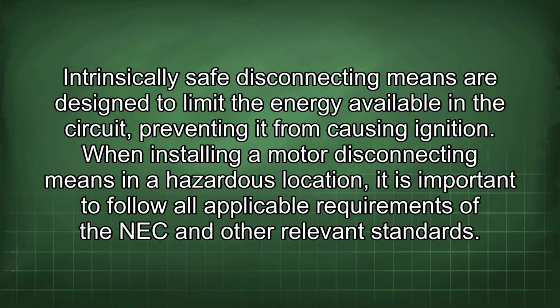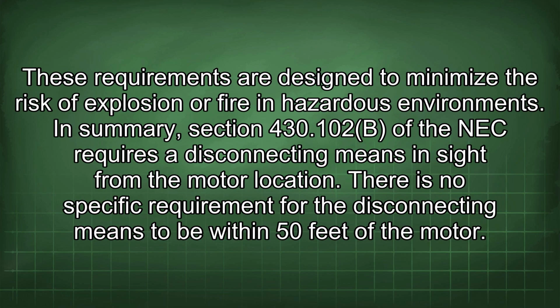When installing a motor disconnecting means in a hazardous location, it is important to follow all applicable requirements of the NEC and other relevant standards. These requirements are designed to minimize the risk of explosion or fire in hazardous environments. In summary, Section 430.102B of the NEC requires a disconnecting means in sight from the motor location.